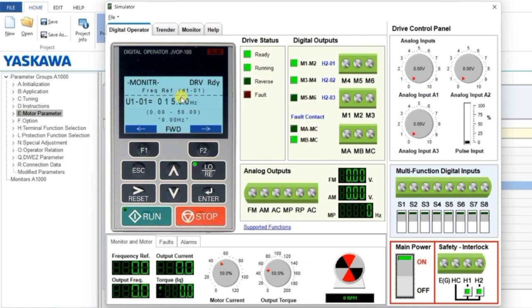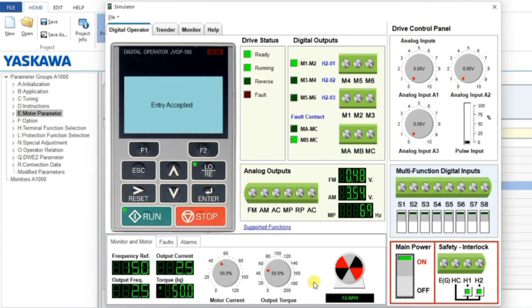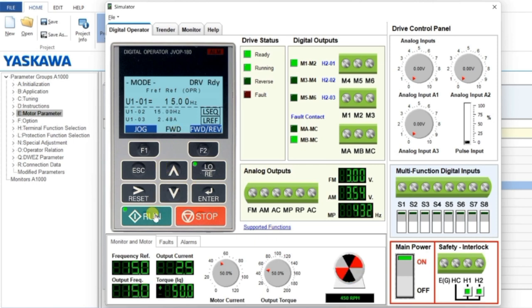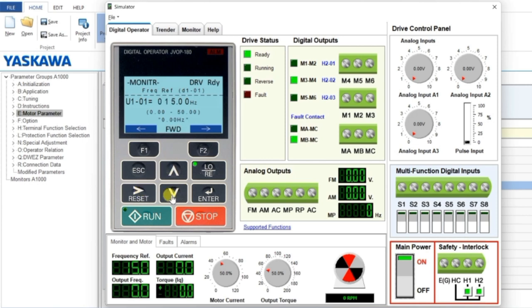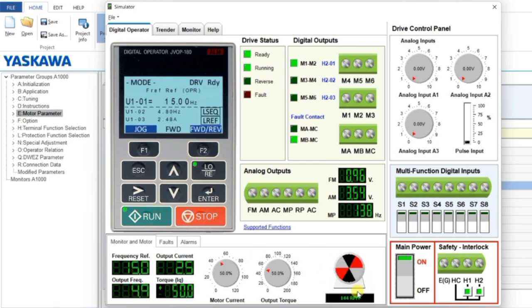You can set any frequency between 0 and 50 Hz, then press Enter. You can see the motor is now running. Click Run to start and Stop to stop the motor. You can see the direction indicator here. If you want to change the frequency, make sure 'Frequency Reference' is selected, then click Enter, set your desired frequency using the keypad, and click Run. You can see the RPMs here - this is operation from the keypad.